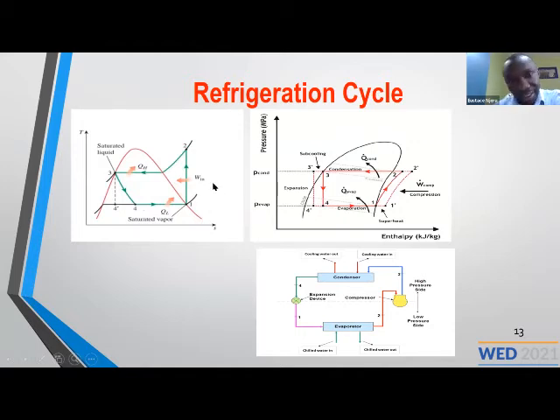So in that case, the chillers have one area in the refrigeration cycle, the compressor, where you have most of the energy being consumed. You need electricity to run the compressor. And that's one of the areas where you can improve on energy efficiency of the chiller, because it is the compressor which directly consumes the energy.